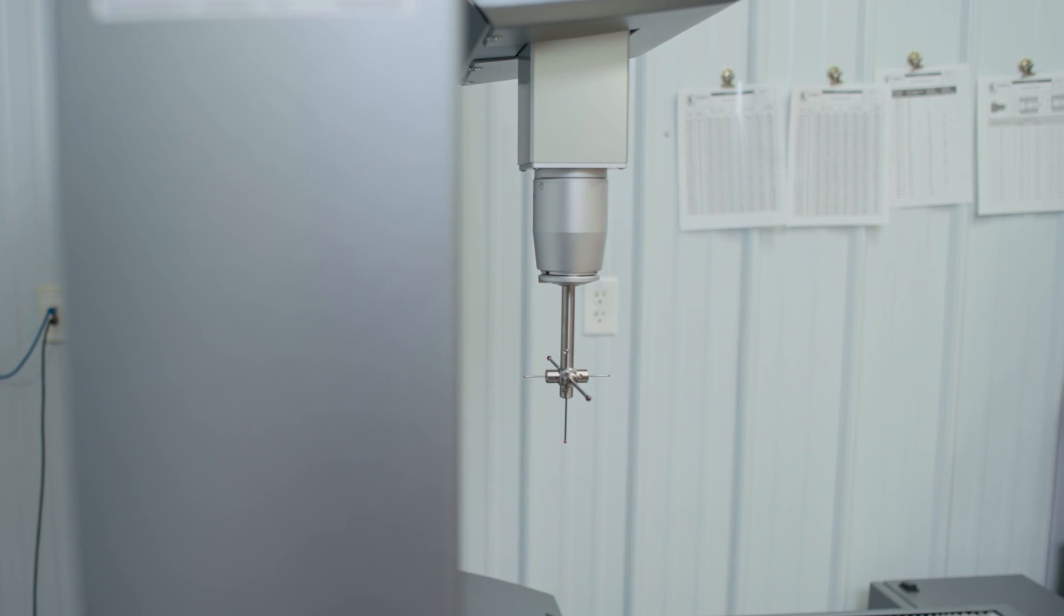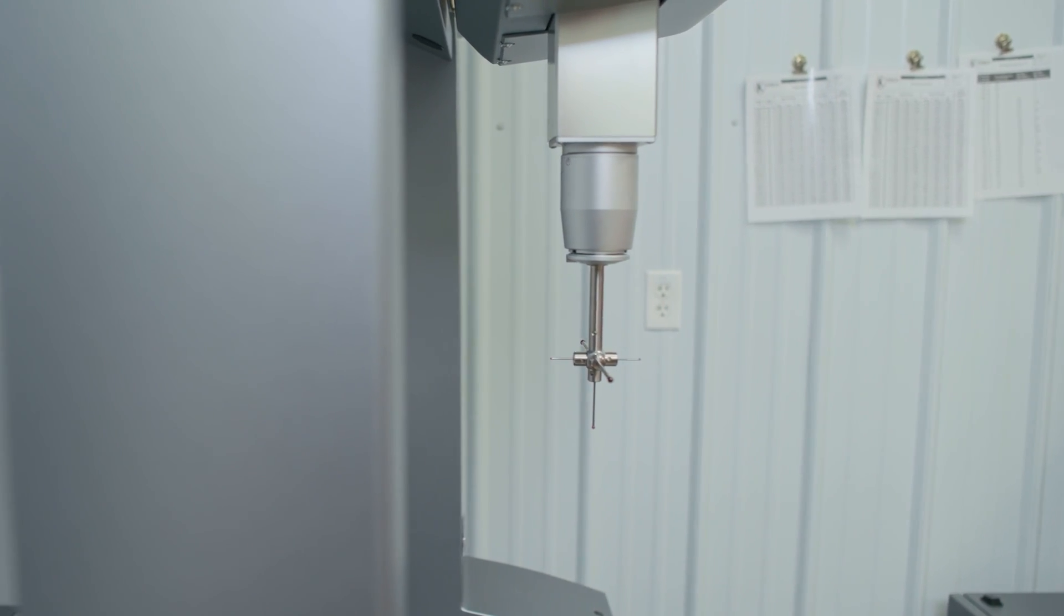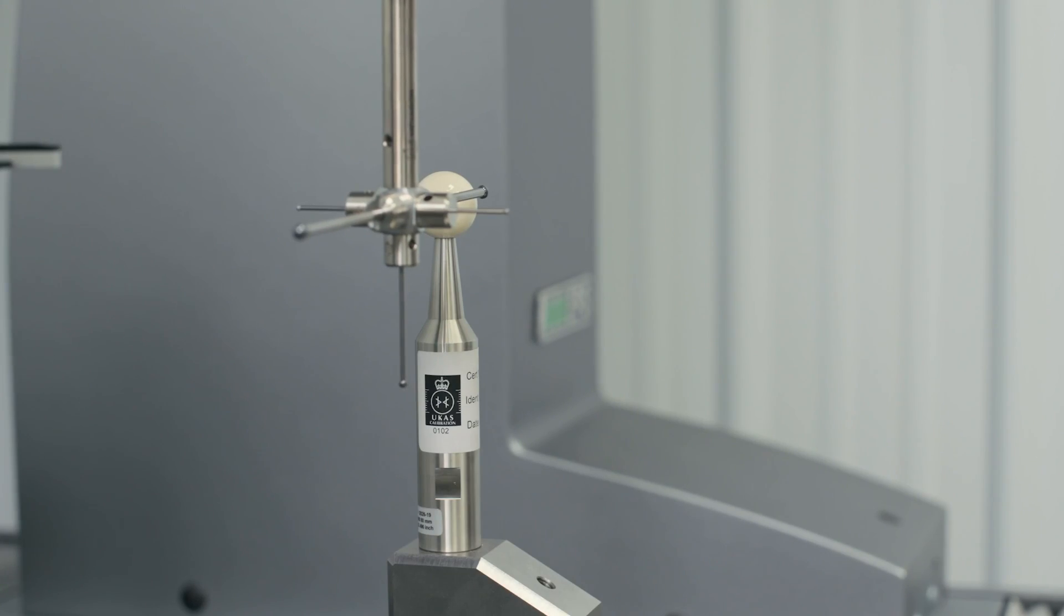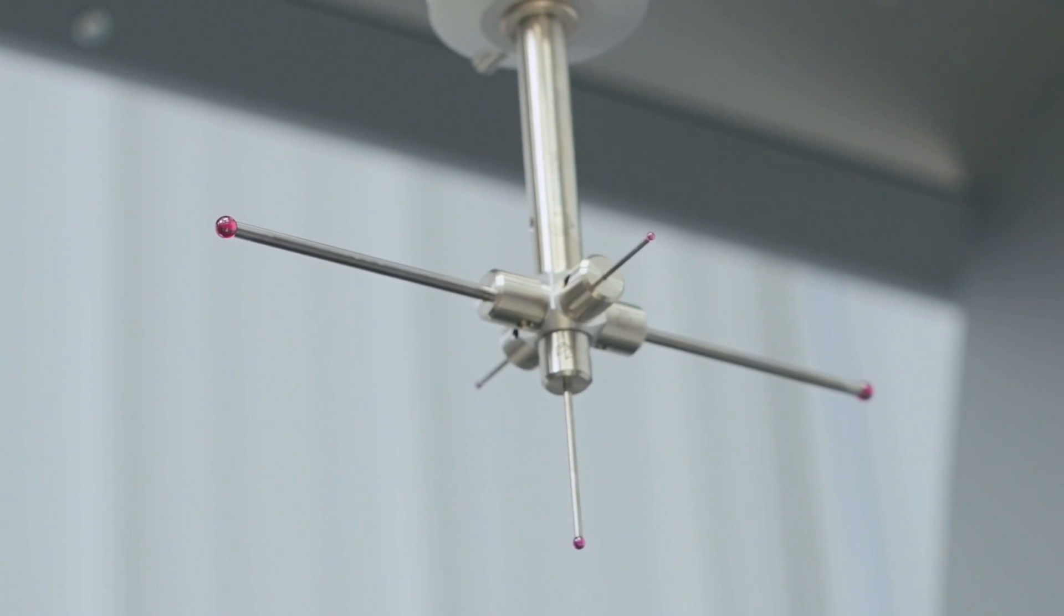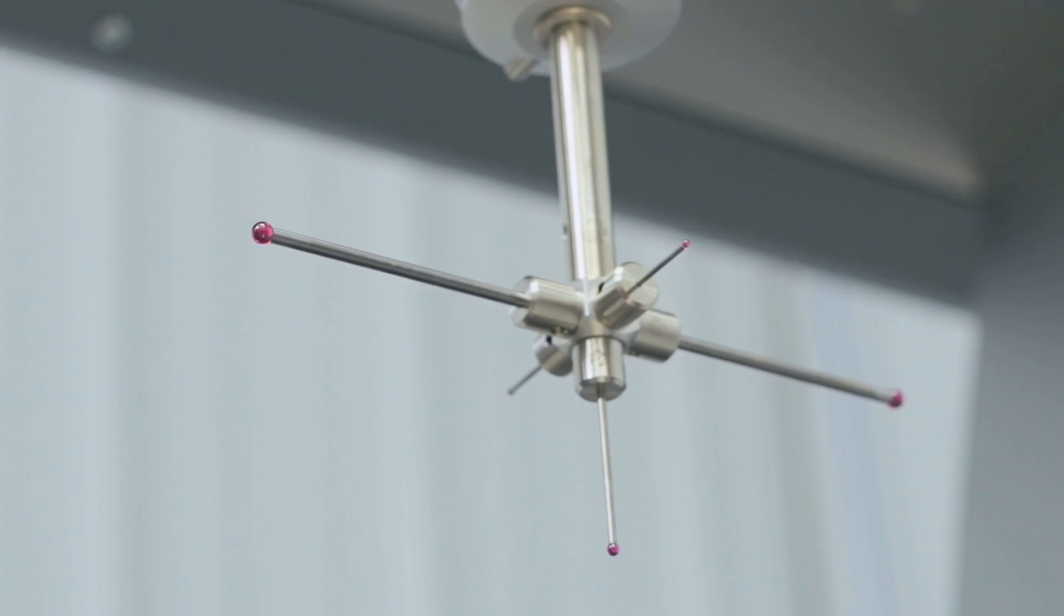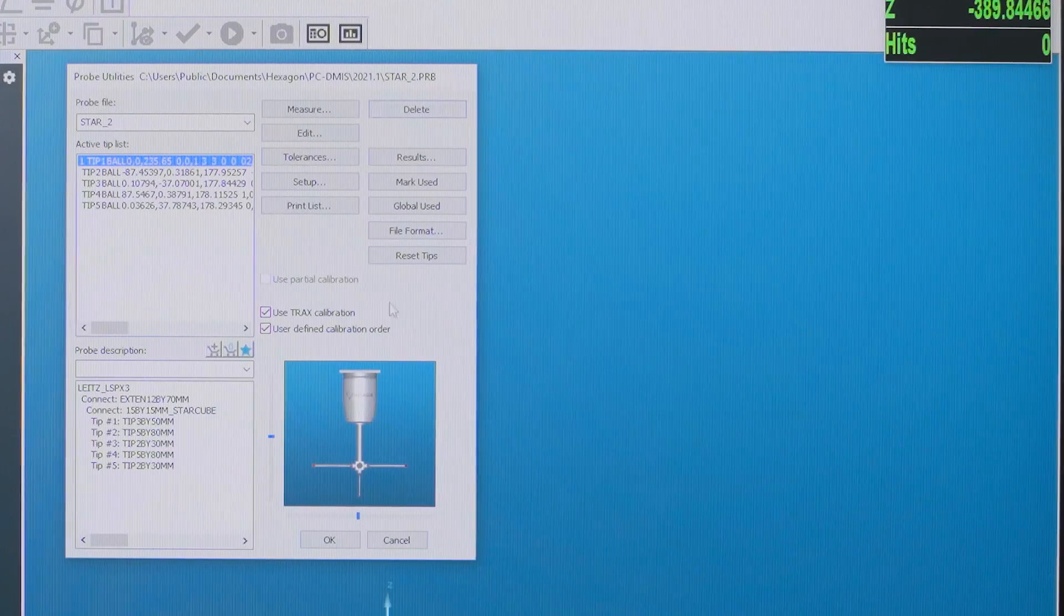Number one is going to be our master tip. When we calibrate this to the sphere, this will be the master probe that all of the other probes will calibrate from that data. So we'll only do this first tip right now.